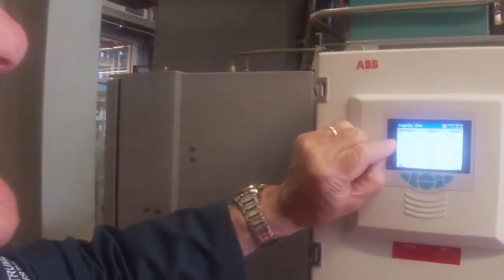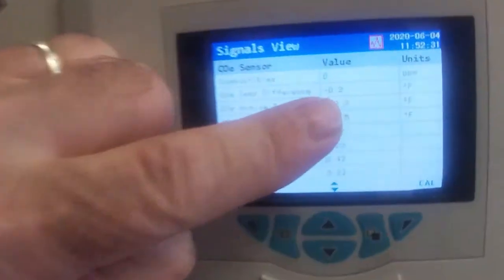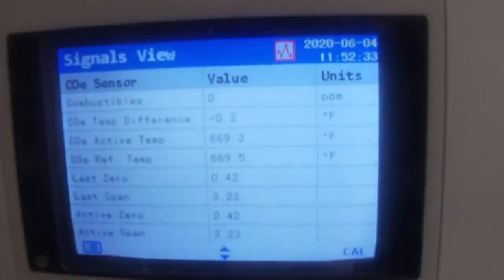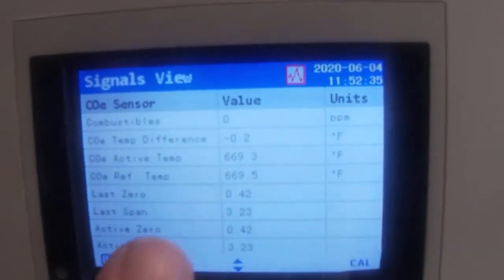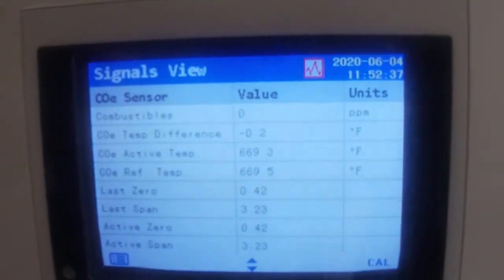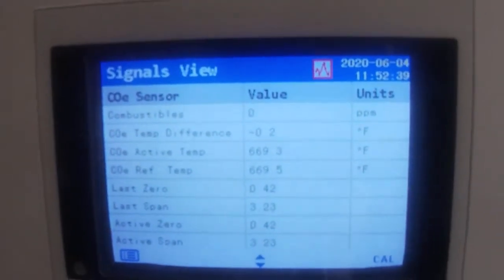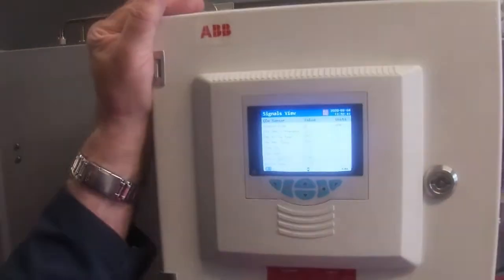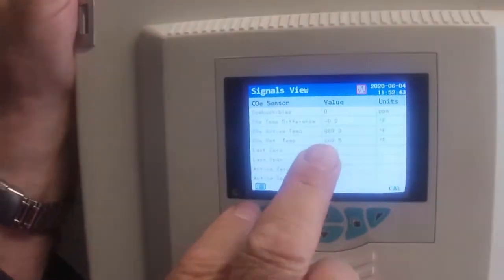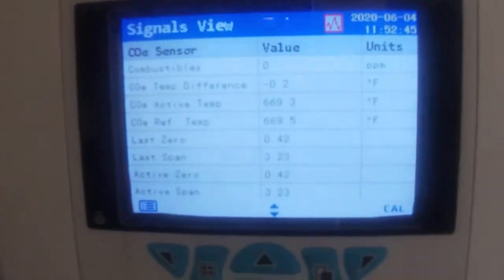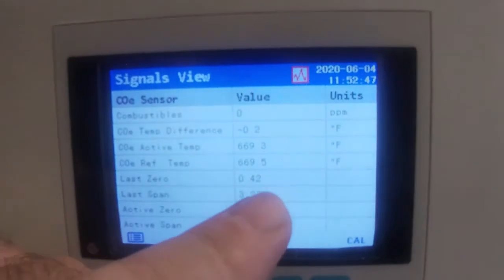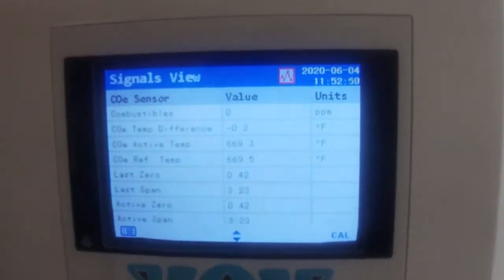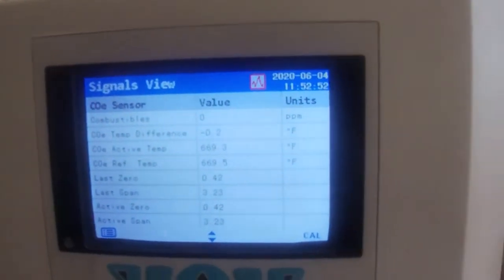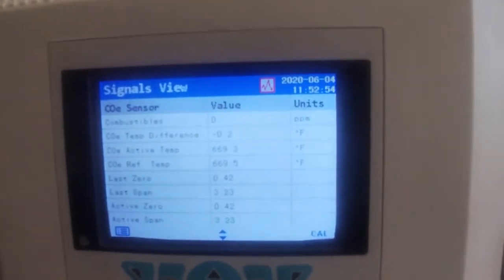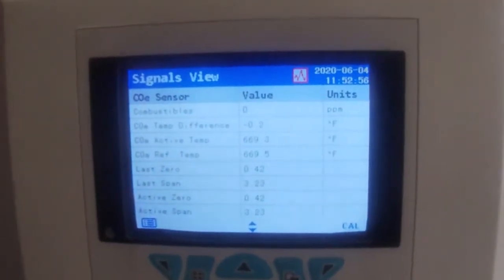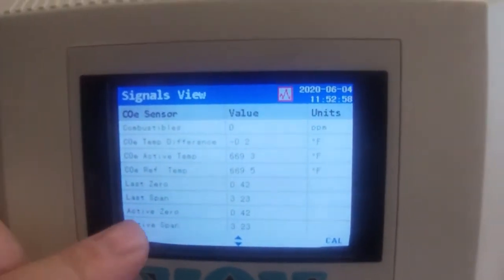Okay, so then the COE temperature difference, the difference between the active and the reference cell, is only at 0.2 degrees Fahrenheit, almost nothing, because there is nothing there. The active temperature is sitting at 669.3 degrees F. The reference temperature is sitting at 669.5 degrees F. And that again is, there's two different cells in there for measuring this combustible.